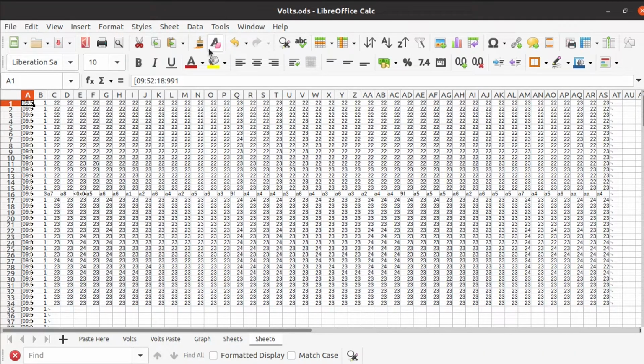So the first spreadsheet here is the data output from the BMS to the laptop. Each row is a list of voltages reported from the BMS for each cell. There are 43 cells. There's a column for the time, and the B column there is 1 or 3 - 1 means volts, 3 means temperature. So it's reporting 29 volts and then 1 temperature, so temperature every 30 times. Then it reports 43 numbers.